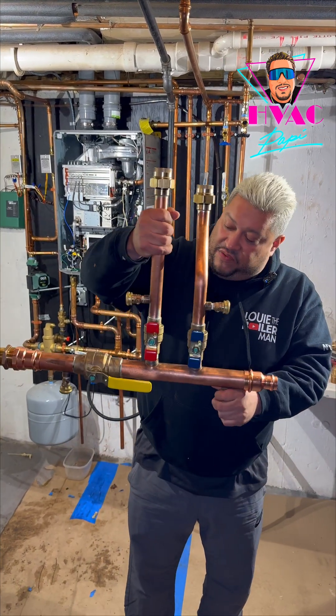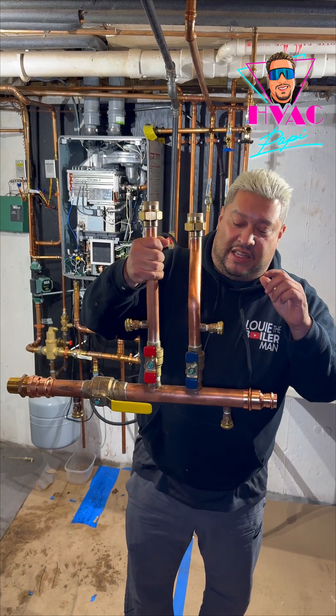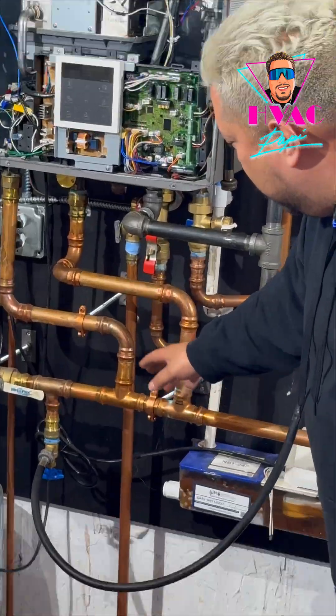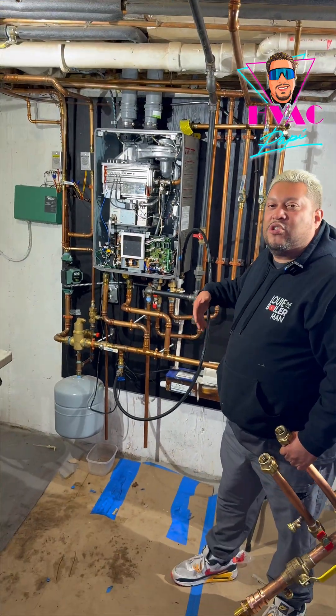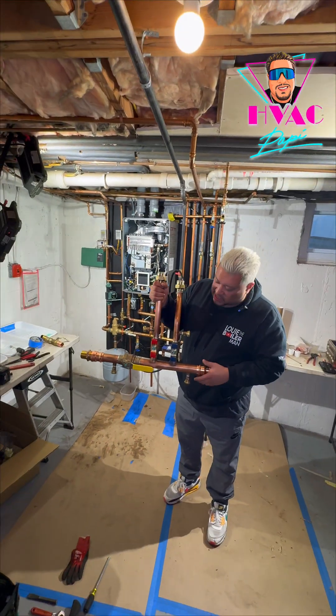So it's right here, guys. The other thing is, you got your isolation valve here, so you can actually descale it. Because notice right here, there's no — how are you going to descale it? There's no valve, there's nothing to connect to, there's no way to actually do the proper service and maintenance. Which is why you're going to use one of these bad boys — Primary Loop.